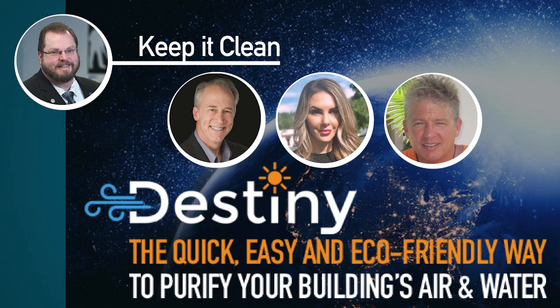Now, for a lot of people, they're going to hear that and say, but I want outside air, because they don't understand why not to. So I'm going to ask, why is that important? That's important because if you're bringing more outside air in, you're reducing your return air. And as you reduce your return air, you're pressurizing the building and moving the germs around the building and not bringing them back to the HVAC system.